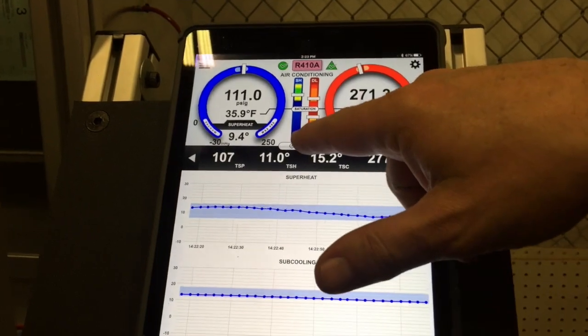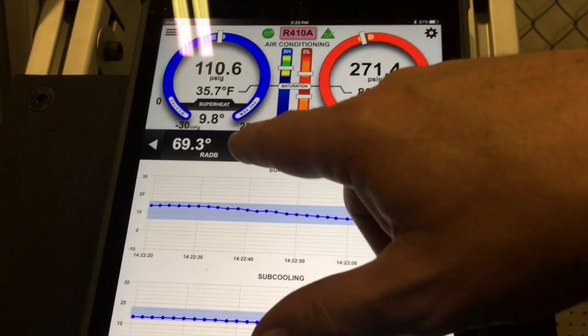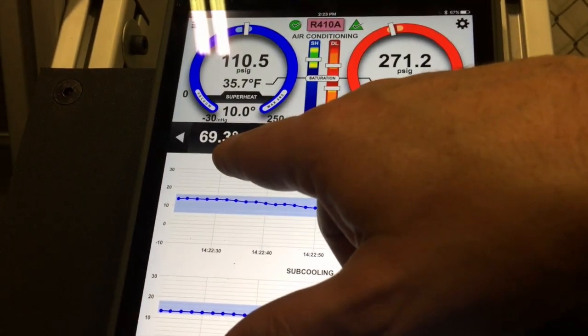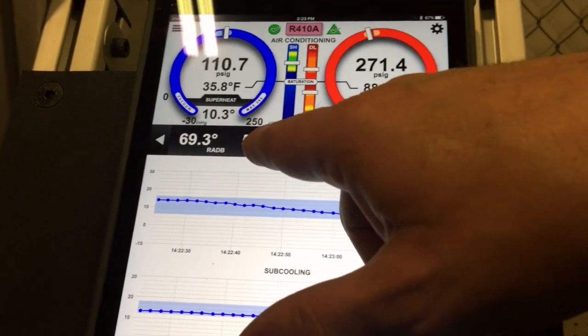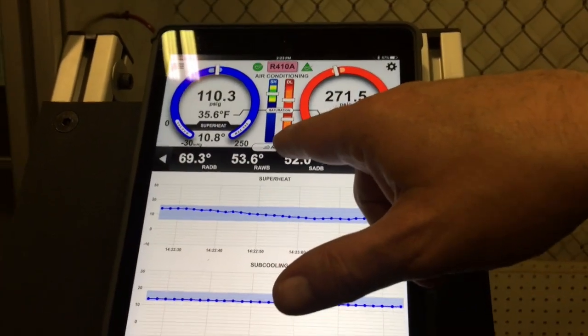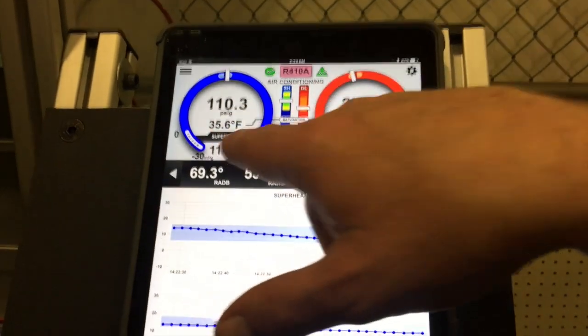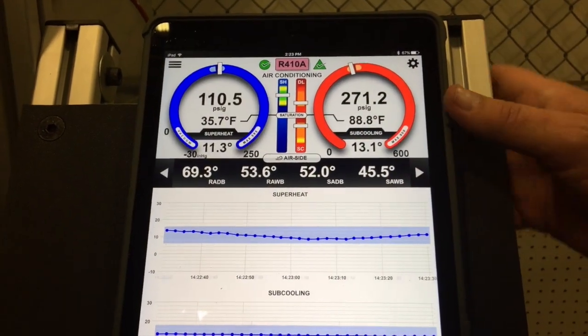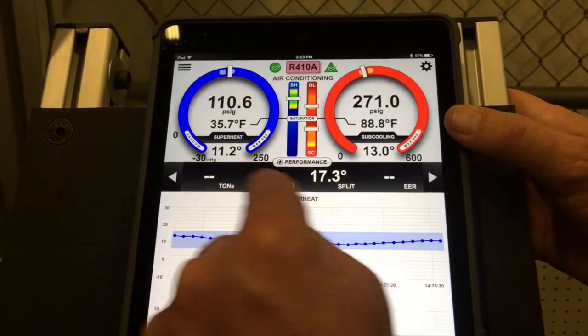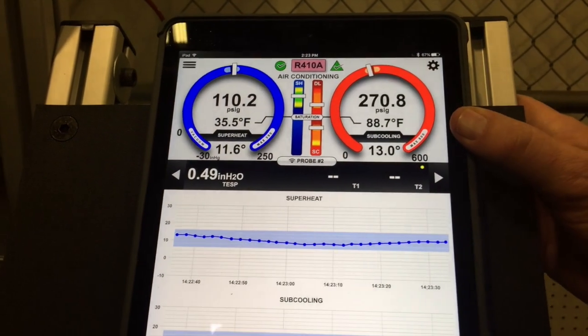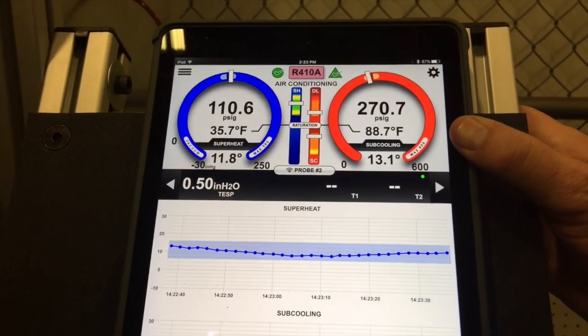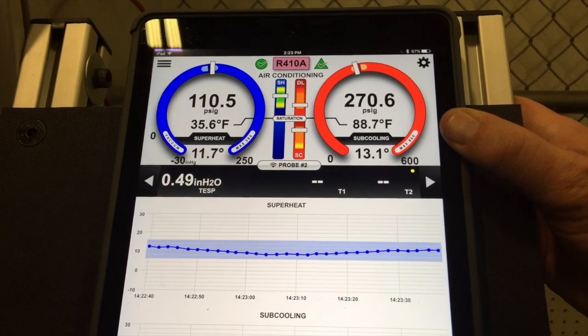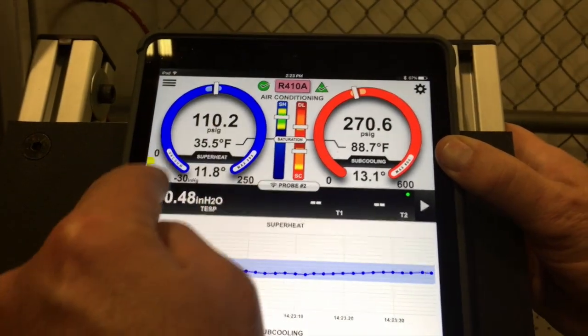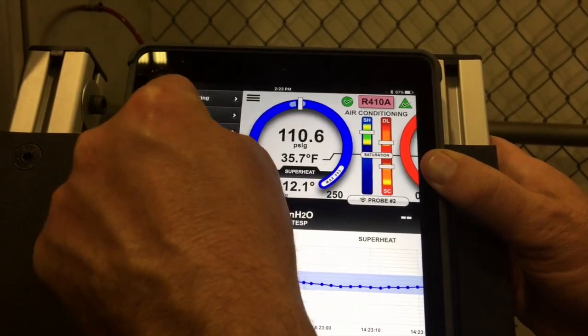Our airflow indicator is not indicating anything because our return air temperature has dropped below 70 degrees. The threshold is 70, so we don't have an airflow calculation. In this case here, what we would do is we would get our total external static pressure, which is a half an inch right now. And if we look at the manufacturer's chart, that's about 1227 CFM. So I'm going to go ahead and put that in our measurement section.